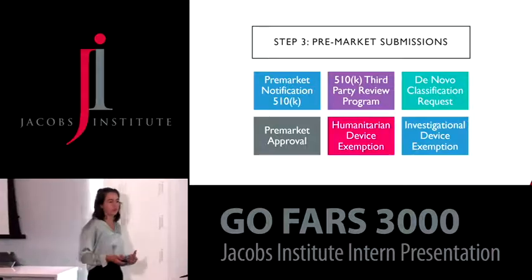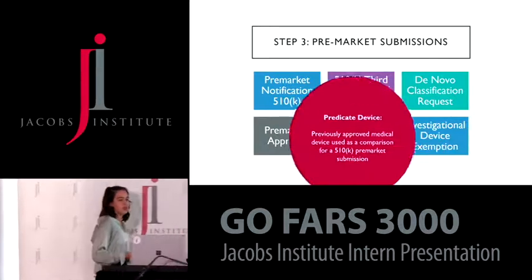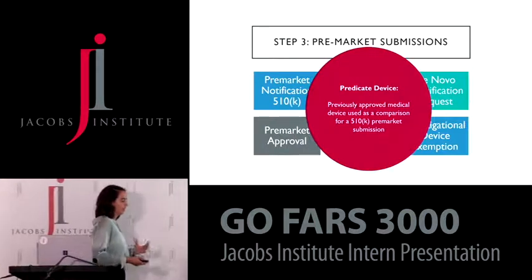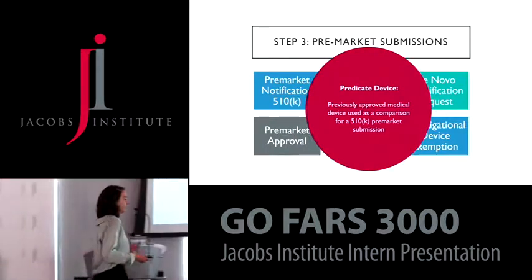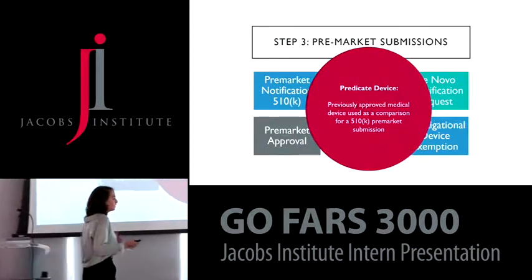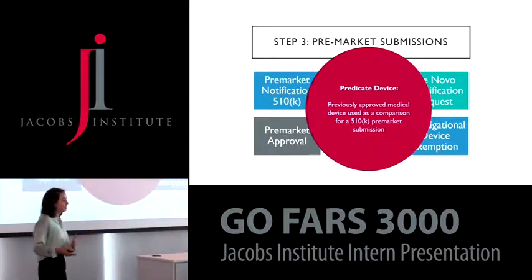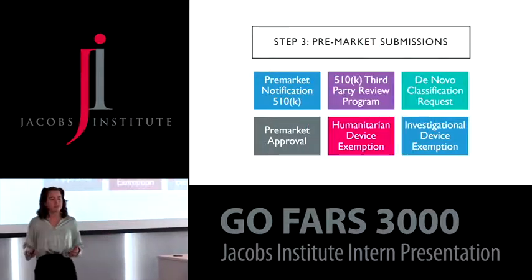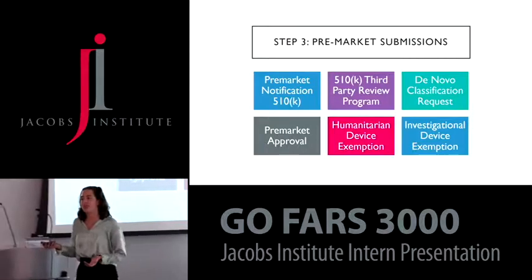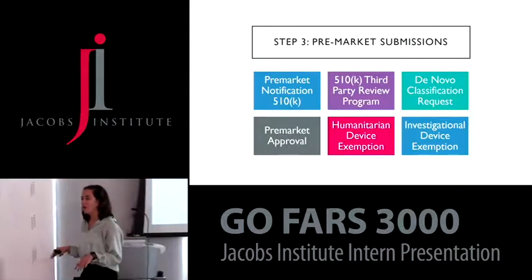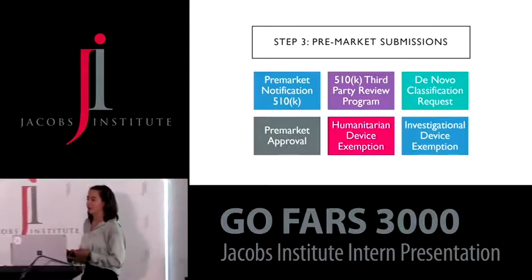In the case of GoFARS, we have a predicate device, and so therefore we will submit for a 510K, which can be thought of as a shortcut submission, where we only need to prove that our device is as effective as our predicate. This differs from, let's say, a de novo request, which starts from ground zero with a brand new device and a brand new indication for use.